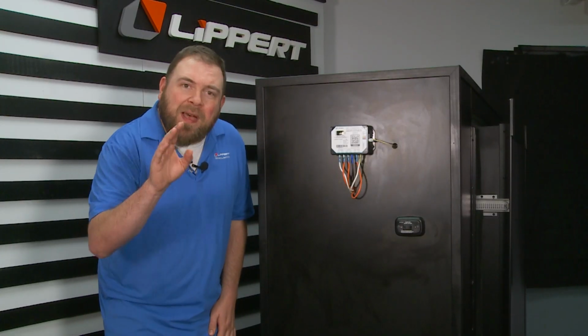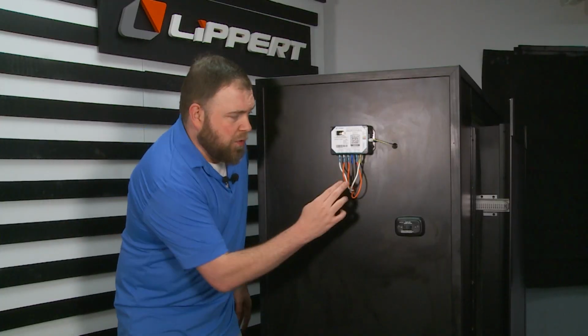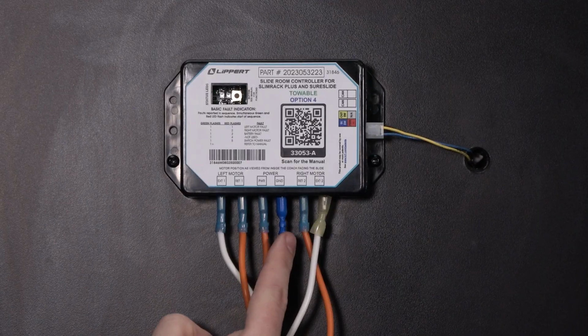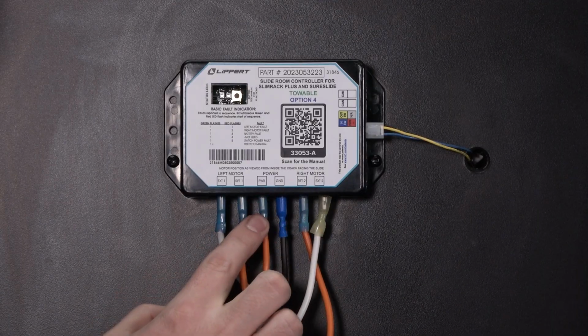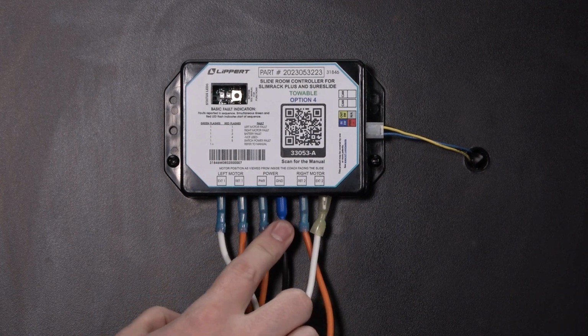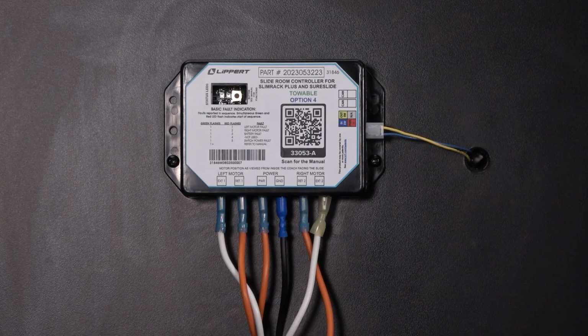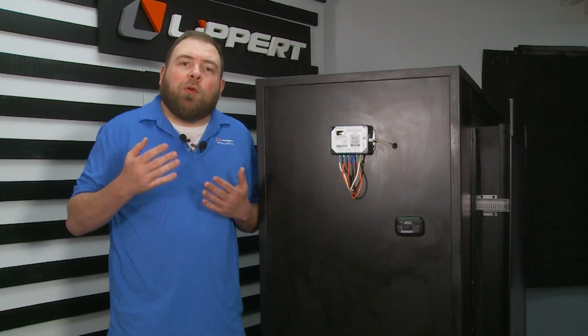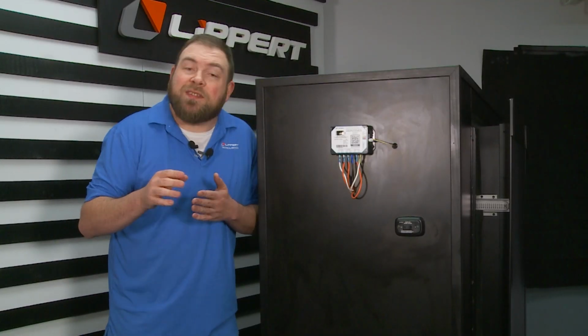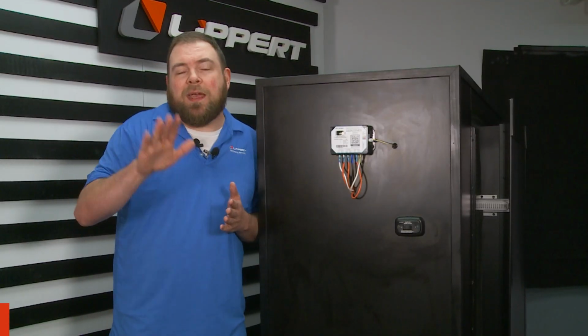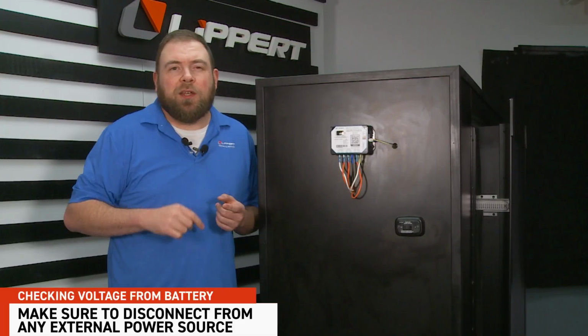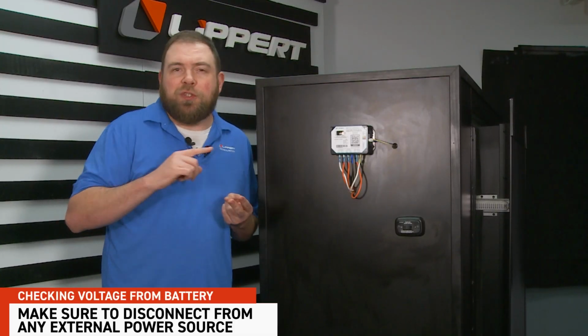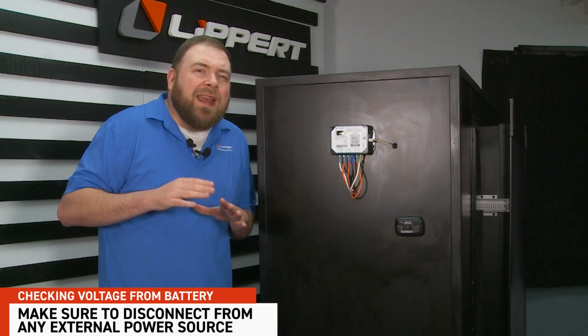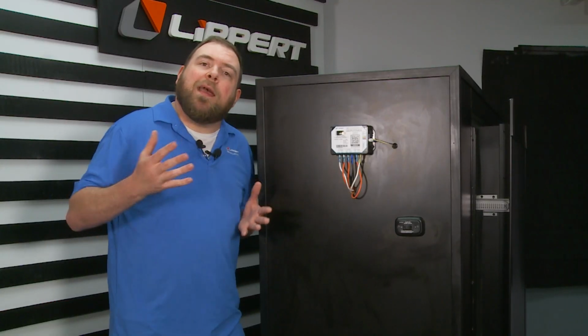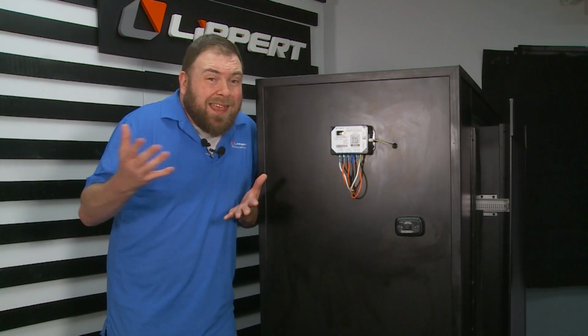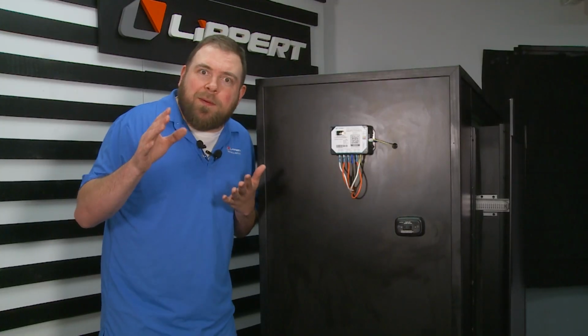Now, the very best first thing we're going to do is probe for power. You'll see on your controller we have a power and a ground signal going right into it, and we need to verify that the voltage is healthy. To do this, I recommend we disconnect from any external power source—no solar panel, no generator, nothing that could possibly inflate the battery voltage and mask an unhealthy battery.